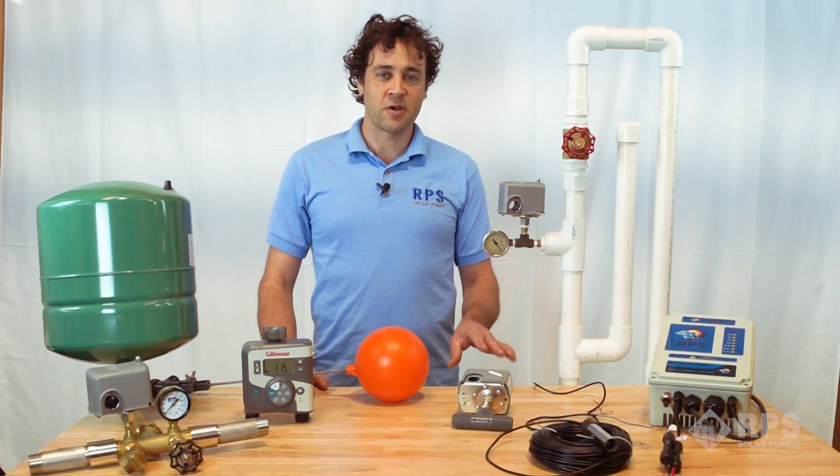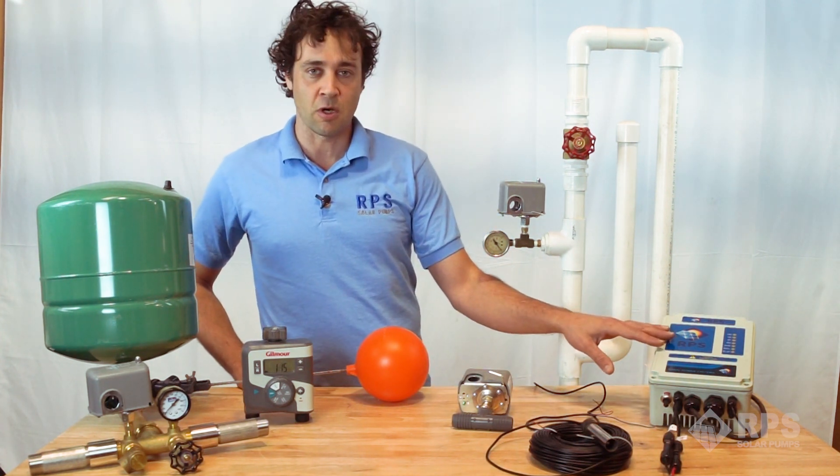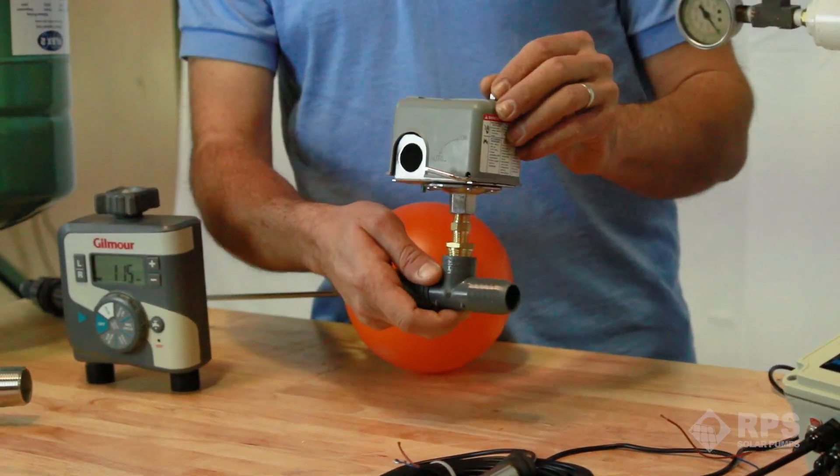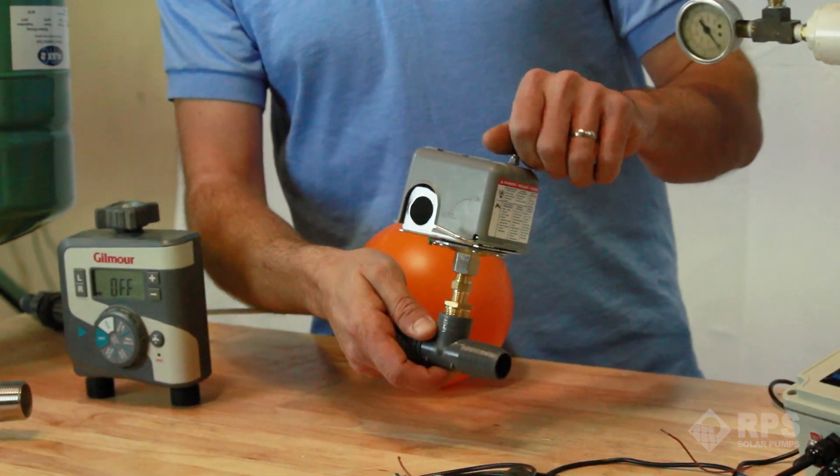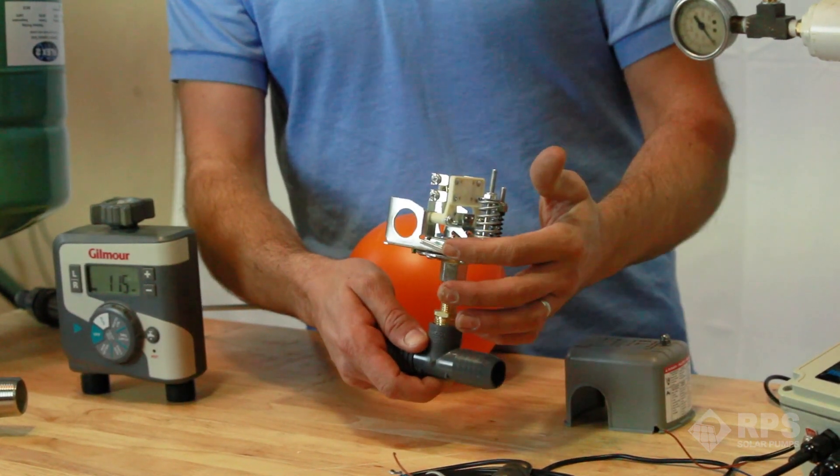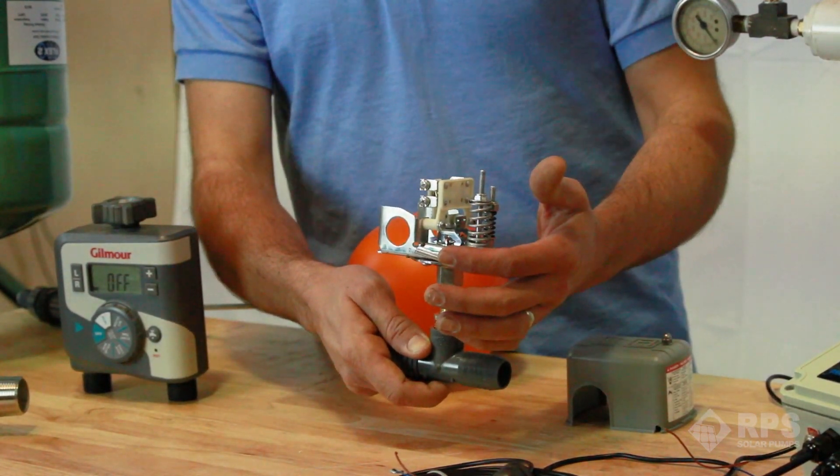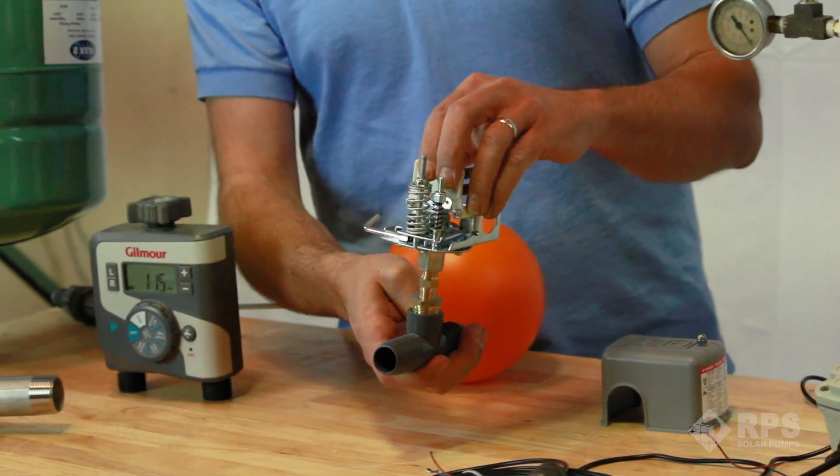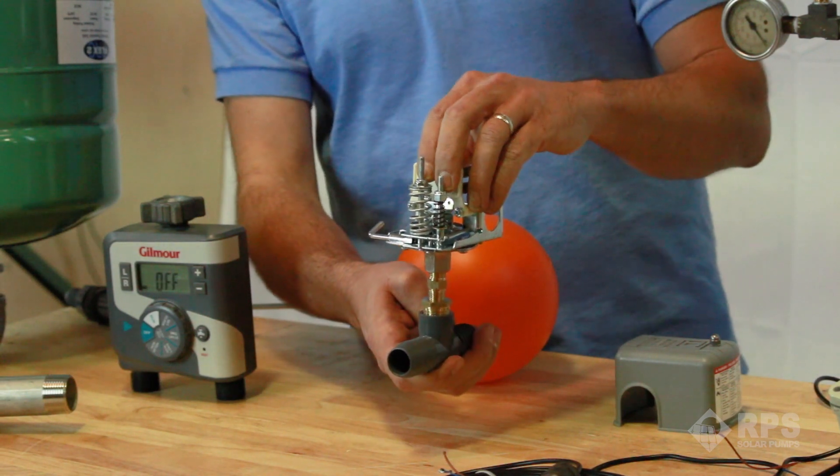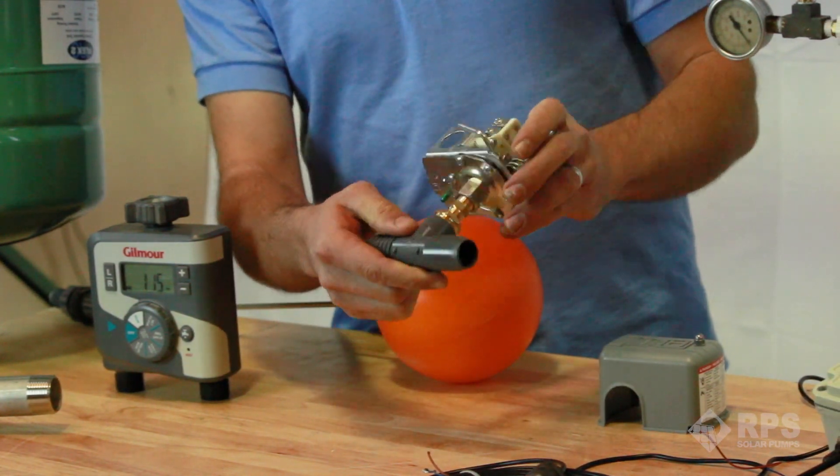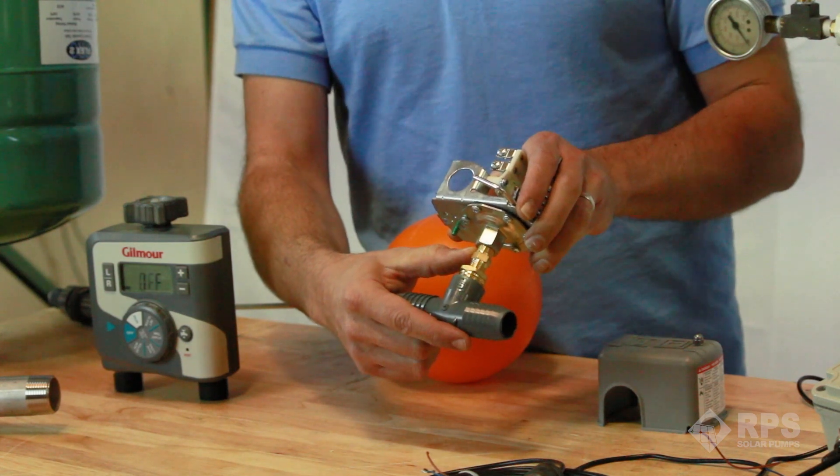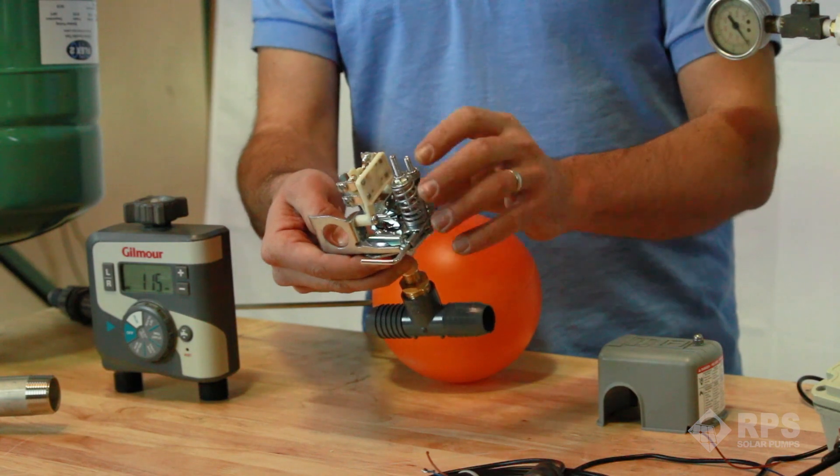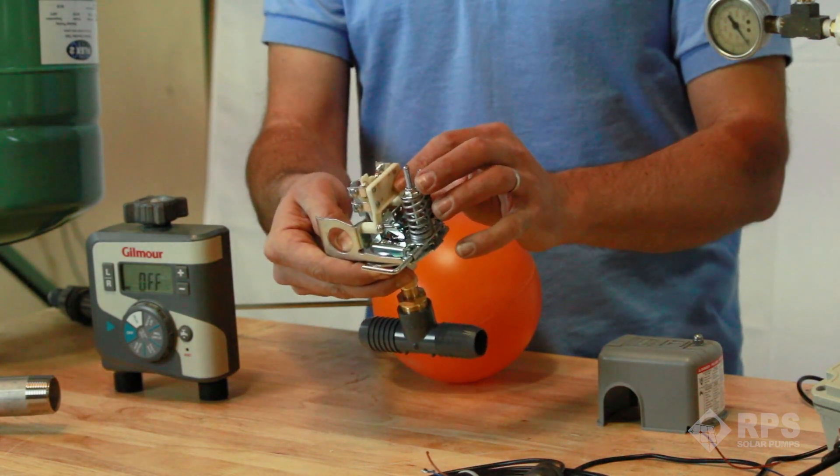We want to talk now about the functions and features of the pressure switch and how it integrates into our RPS solar system. What you have here is a pressure switch with the all-weather cover. We'll take this off. You can see on the front there's a lever that allows you to select the different mode that the pressure switch will operate in. There's some spring-loaded adjustment bolts right here and we'll get to those later, and then on the bottom this is the pressure port that sends the water signal to a diaphragm down below that translates that into whether or not the switch will remain open or closed.